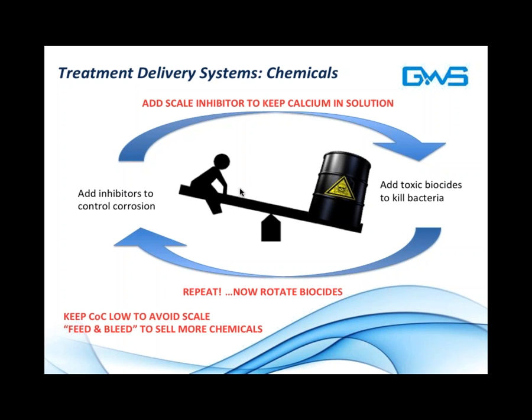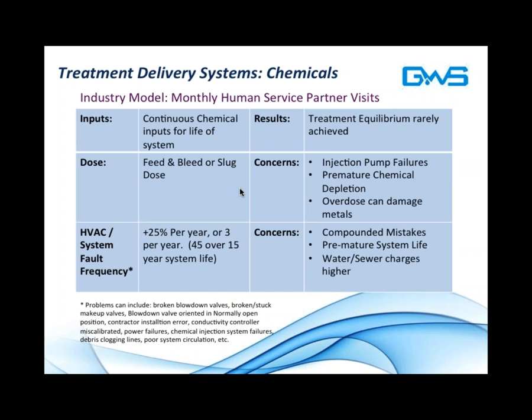So many service partners will do what's called feed and bleed, which is to say keep cooling systems running at artificially low cycles of concentration. And by doing so, they eliminate the risk of scaling. They also waste more water and therefore can sell more chemicals, because more chemicals go in and therefore more chemicals go out in the drain. Again, reputable service partners will not do this, but those that own blending shops are predisposed to this simply because they have an incentive here to sell more chemicals. That's just the name of the game.